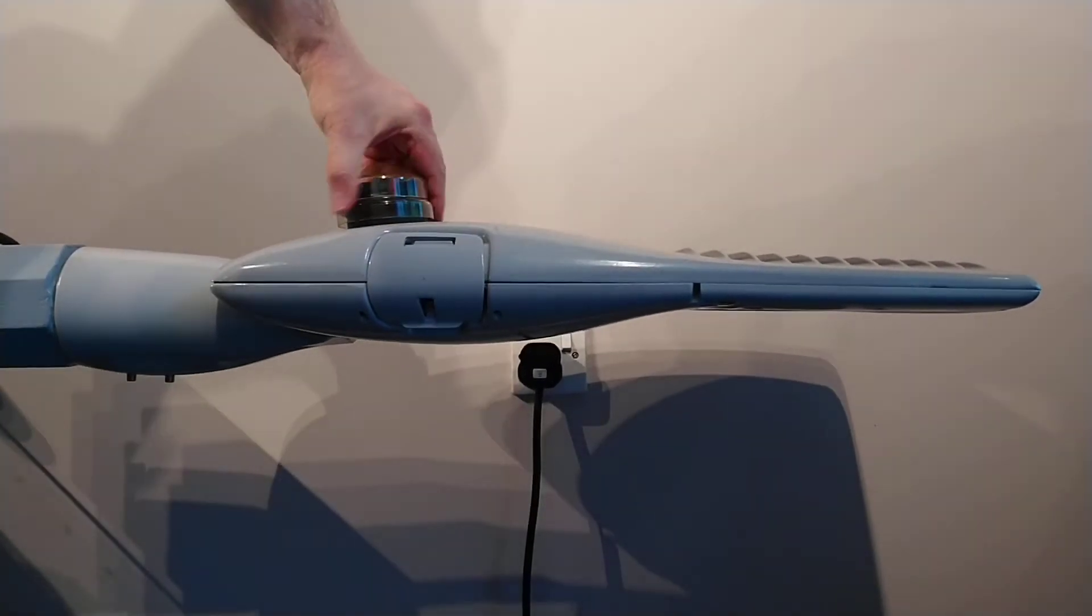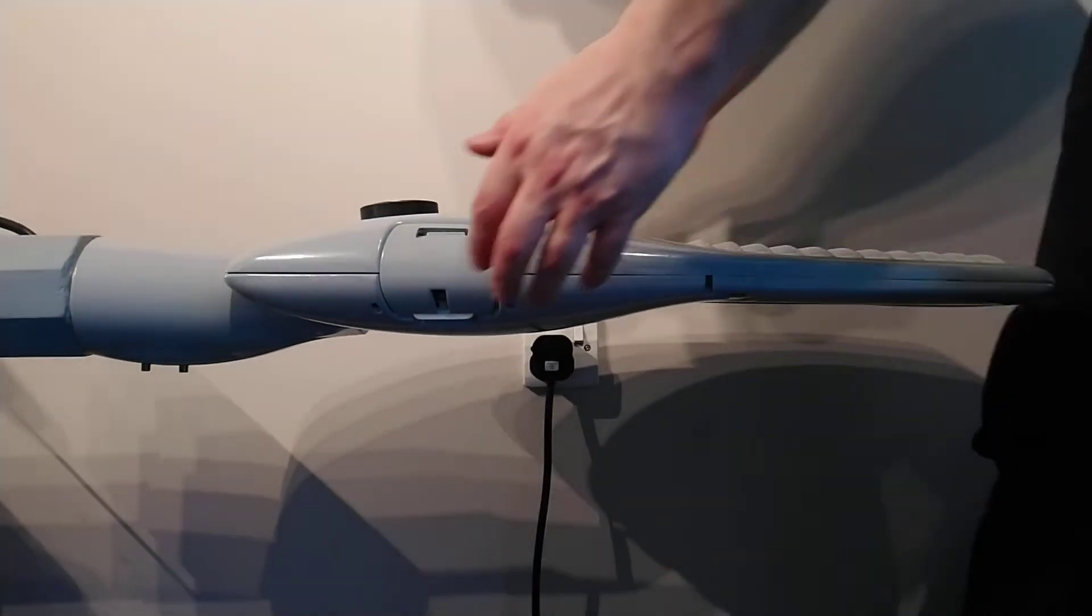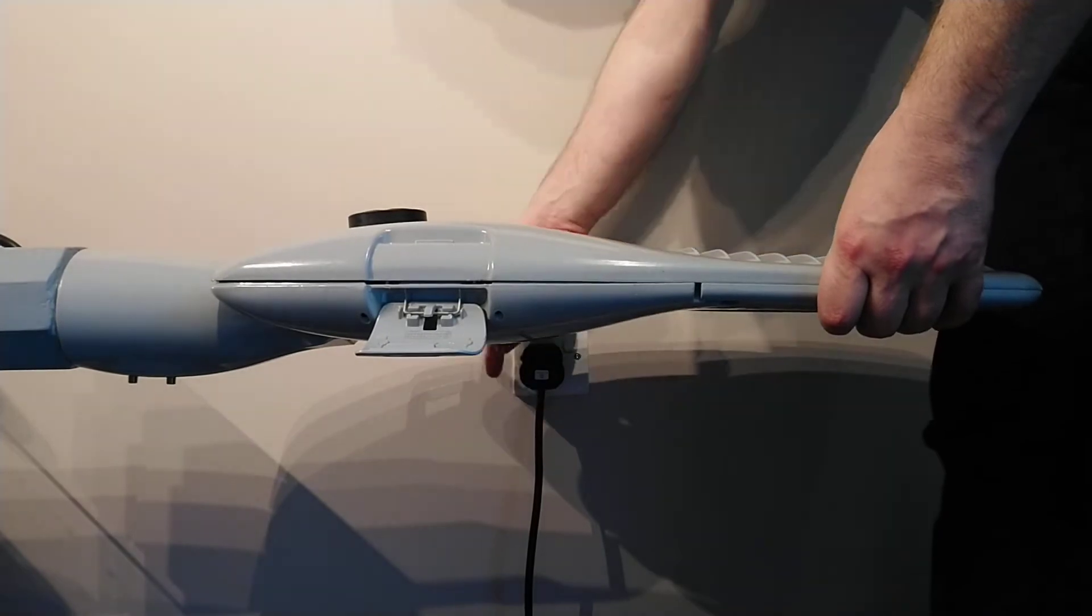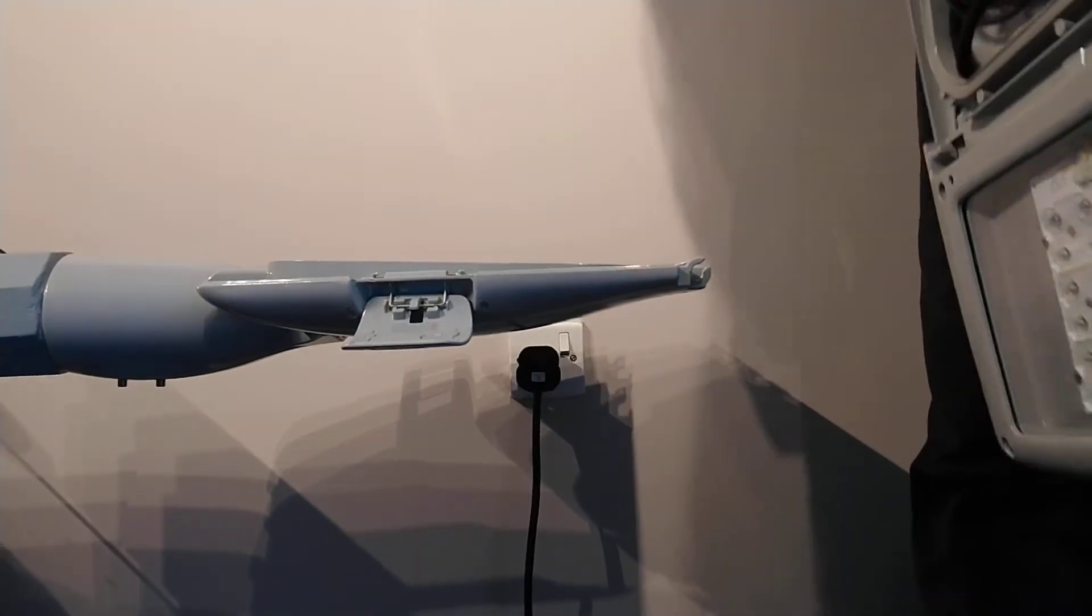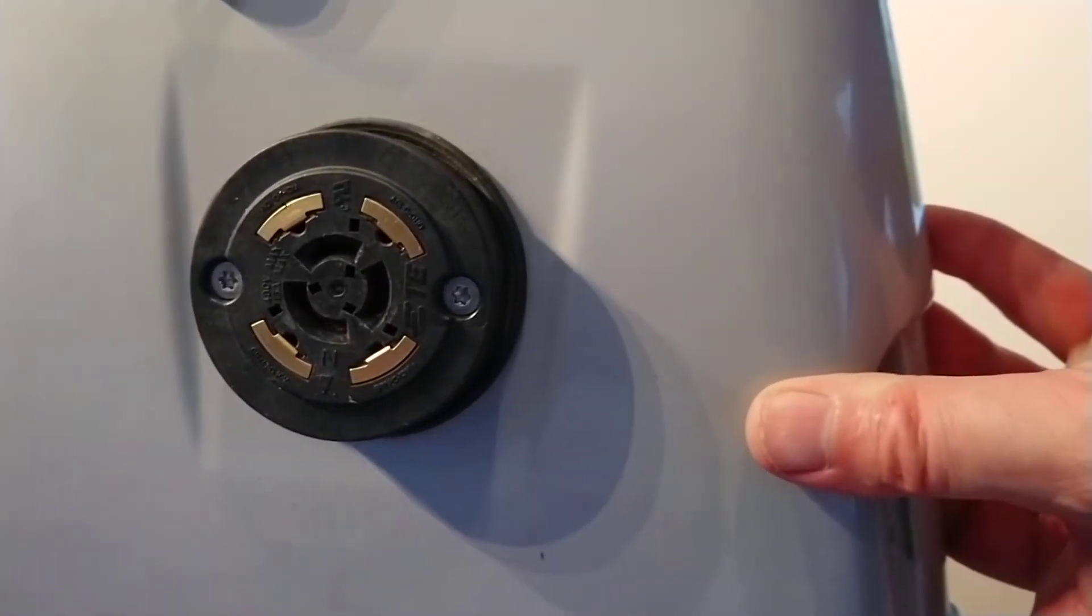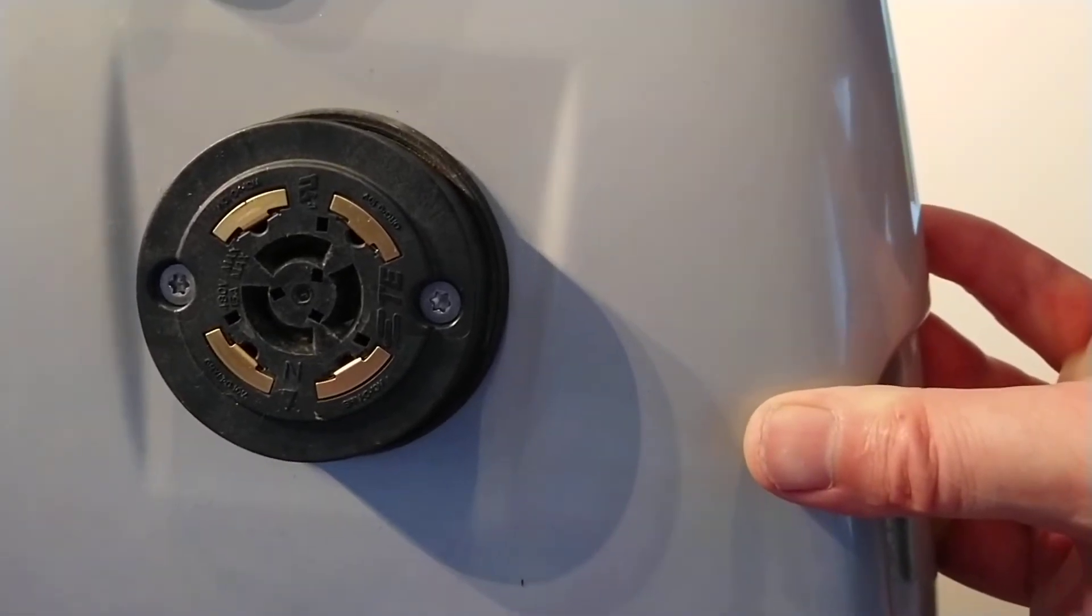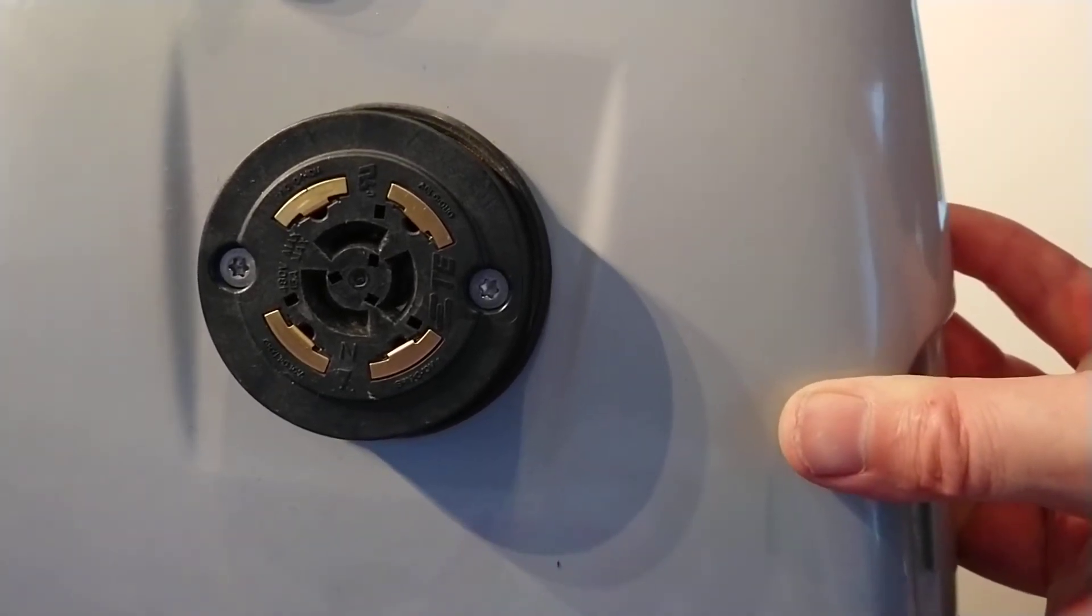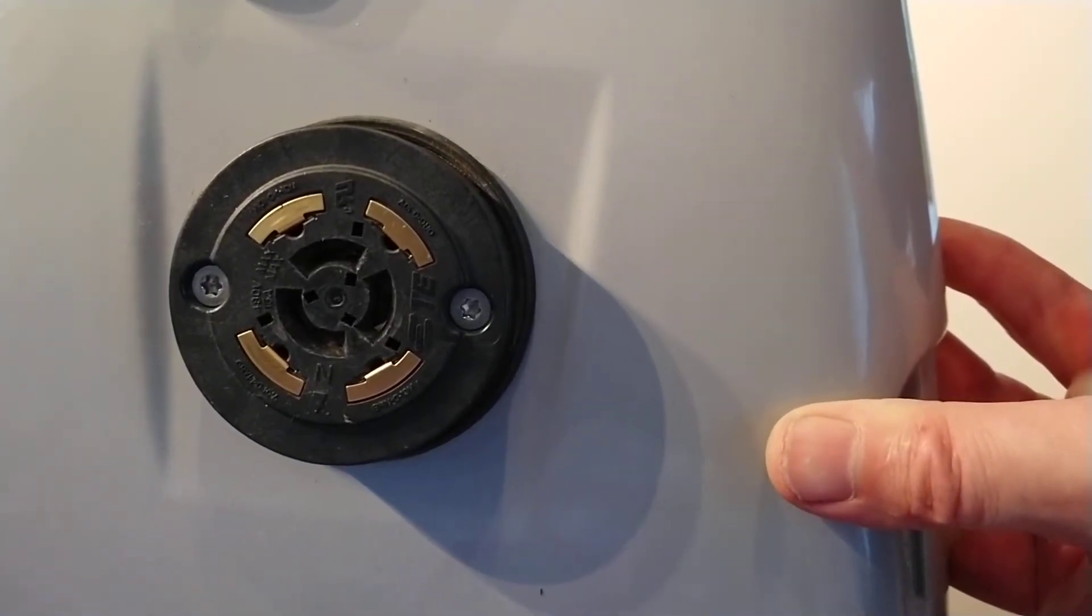Remove the photo cell and unclip the light. To remove these tops, all you have to do is undo the two clips - the light hinges down and then just releases. Now the reason why I'm showing you the photo cell is because these photo cells are designed to have three main connections in the middle and the four outer ones. Bearing in mind the four outer ones are surface mounted and there is live 240 mains going to at least one of them, so you don't really want to touch the top of one of these lights without a photo cell on it.